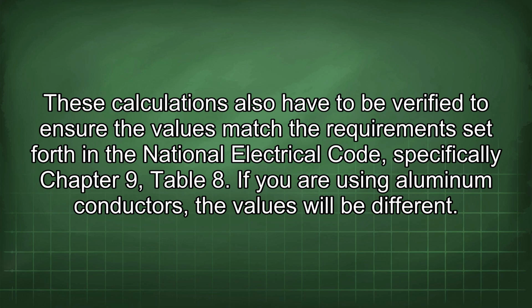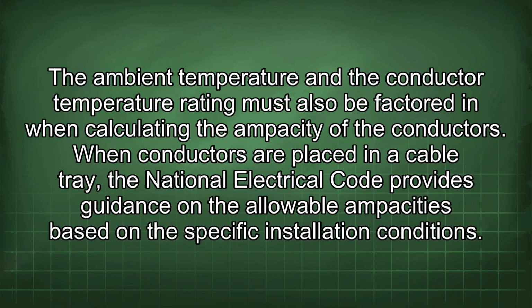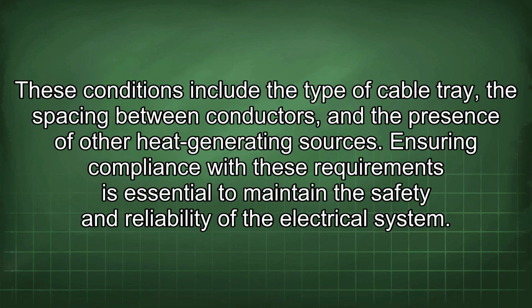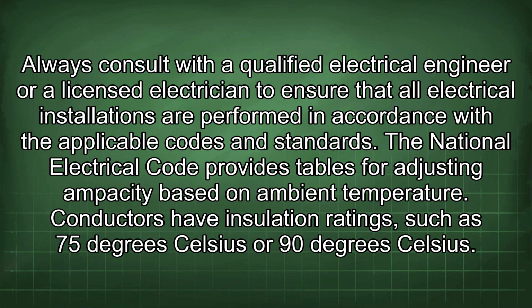These calculations also have to be verified to ensure the values match the requirements set forth in the National Electrical Code, specifically Chapter 9, Table 8. If you are using aluminum conductors, the values will be different. The ambient temperature and the conductor temperature rating must also be factored in when calculating the ampacity of the conductors. When conductors are placed in a cable tray, the National Electrical Code provides guidance on the allowable ampacities based on the specific installation conditions. These conditions include the type of cable tray, the spacing between conductors, and the presence of other heat-generating sources. Ensuring compliance with these requirements is essential to maintain the safety and reliability of the electrical system. Always consult with a qualified electrical engineer or licensed electrician to ensure that all electrical installations are performed in accordance with the applicable codes and standards.